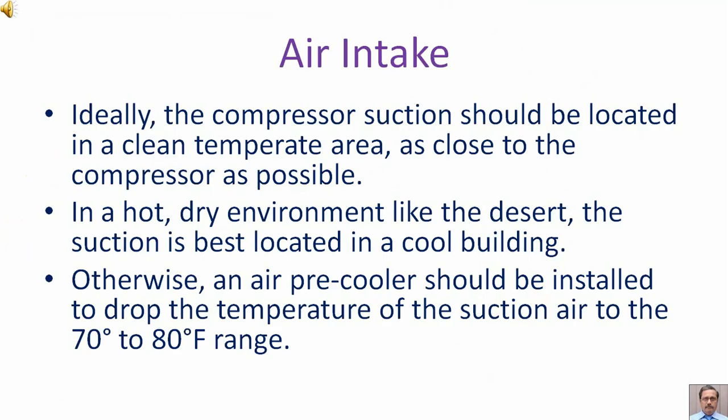Air Intake: Ideally, the compressor suction should be located in a clean, temperate area as close to the compressor as possible. In a hot, dry environment like the desert, the suction is best located in a cool building. Otherwise, an air pre-cooler should be installed to drop the temperature of the suction air to the 70°F to 80°F range.